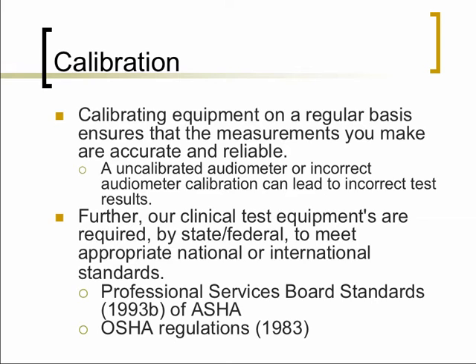And further, from a legal perspective, it's important. You're mandated, in fact, by state and federal agencies to meet some national and international standards. Some of the standards include the Professional Services Board standards, and at a more federal level, it would be the Occupational Safety and Health Administration regulations. And you might find yourself in some legal trouble if you were called upon to confirm the diagnosis of an individual. You need to provide evidence that you've been using calibrated equipment, and there are some cases where one would need to show their calibration certificate and that they've been maintaining at least an annual calibration if there were any medical legal concerns.